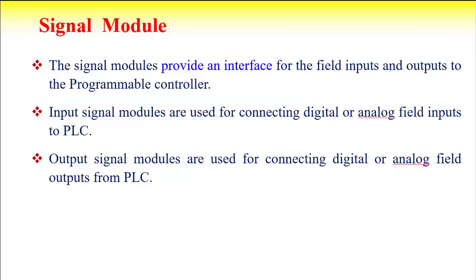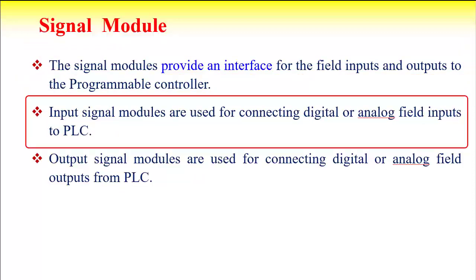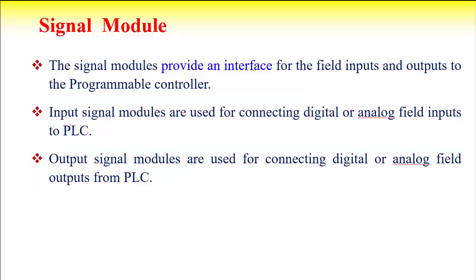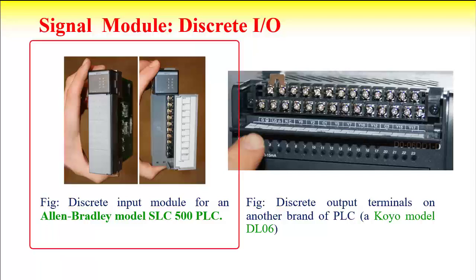Signal modules provide an interface for the field inputs and outputs to the programmable controller. Signal modules are directly connected with field devices and send signals from the field devices to the PLC. Input signal modules are used for connecting digital or analog field inputs to PLC. Output signal modules are used for connecting digital or analog field outputs from PLC to output devices. This is an example of a discrete input module from Allen Bradley model SLC 500 PLC, where 8 inputs can be connected.